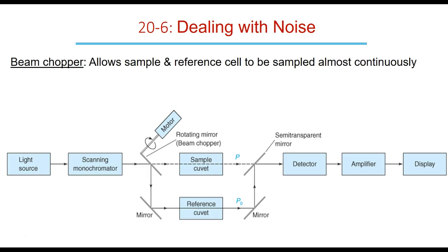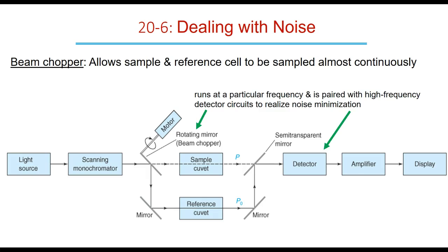But your motor, anything that's motorized, that's doing this cool stuff, it's really helping the instrument, and that's how we can do this beam chopping and have a double beam. But you've just introduced a new noise source. So how are you going to get rid of it? Because we're all about getting rid of noise or minimizing it to a huge degree. Well, it's actually pretty easy.